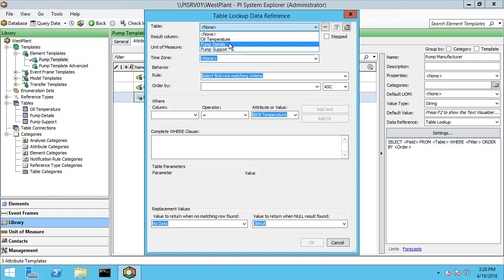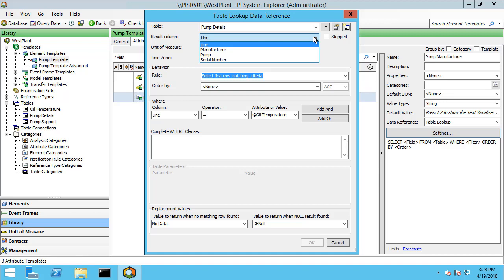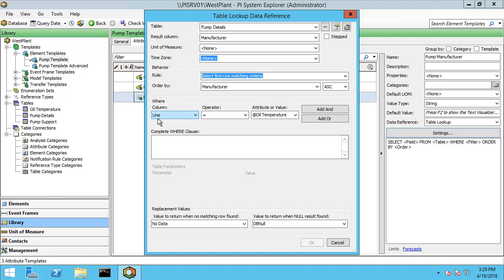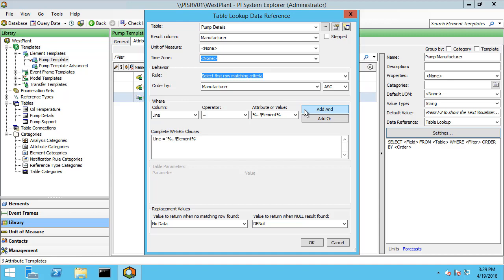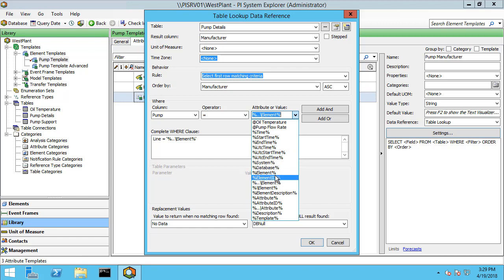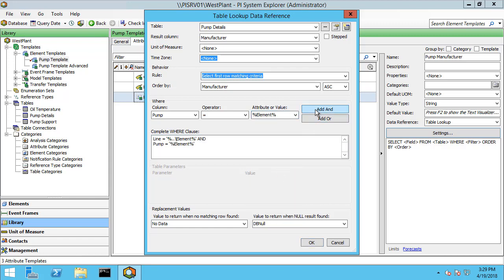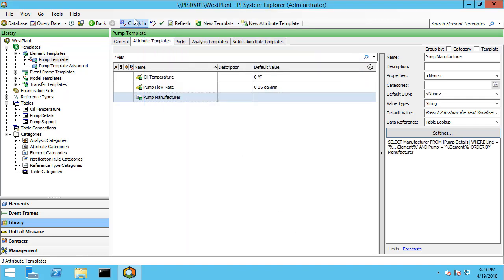The table that we want to use for our table lookup is the pump details table, and the resulting column that we want in our attribute is the name of the manufacturer. Now we need to configure our WHERE clause to bring in the correct manufacturer. The first condition is that the line number is equal to the name of our parent element — the element that's just one level above the inlet pump — and to do that we're going to use this substitution parameter here and click Add. Now we also need to use the inlet pump versus outlet pump to pick up the right manufacturer, so our pump needs to be equal to the name of our current element, which is inlet pump, and click Add. Now we have two conditions that must be met for it to pick up the correct row in the table and return the name of the manufacturer. Go ahead and click OK and check in my changes.